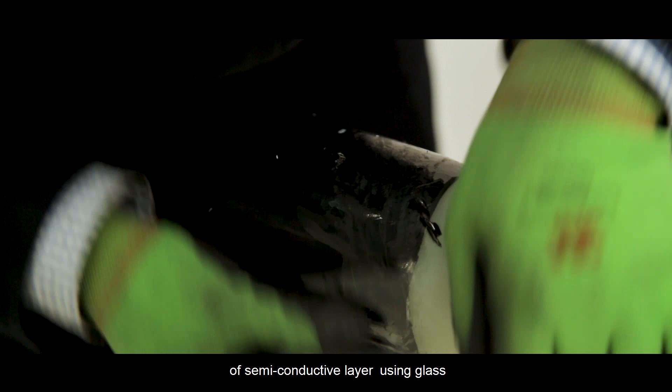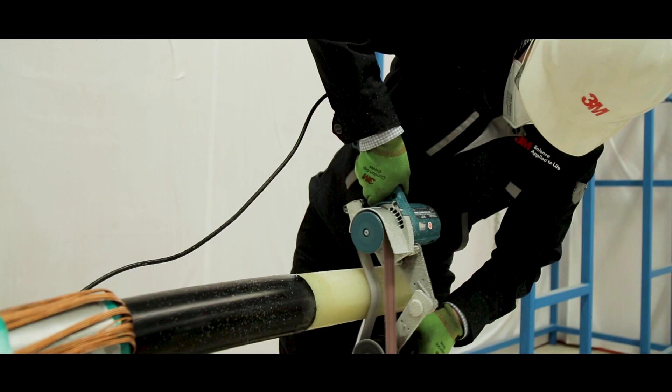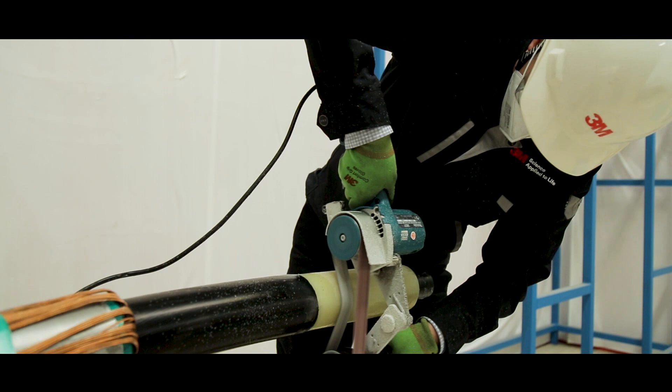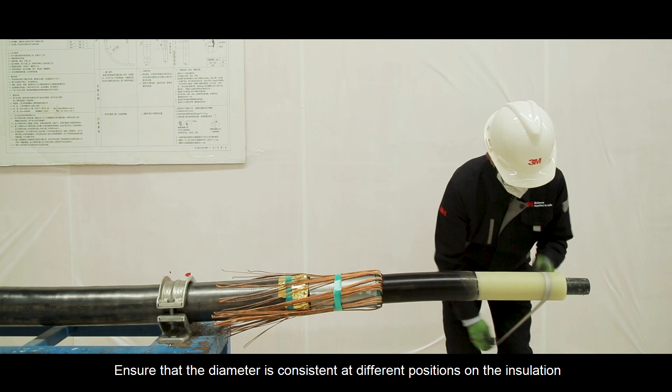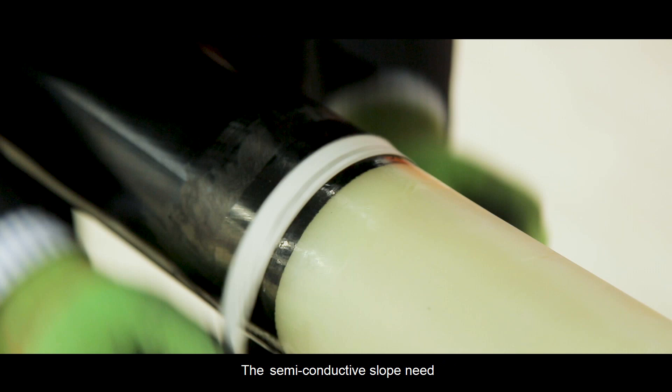Make 30mm smooth slope on the edge of semi-conductive layer using glass. Abrade the insulation with sanding machine and then change to manual sanding. Ensure that the diameter is consistent at different positions on the insulation and make sure there are no cuts or defects. The semi-conductive slope needs to be manually abraded and polished.